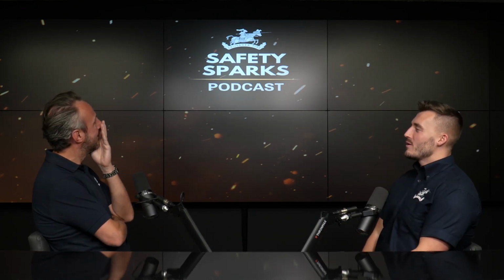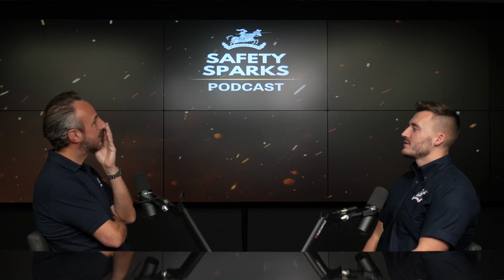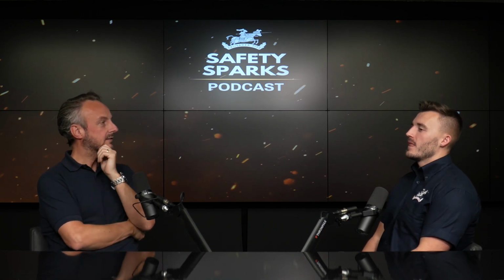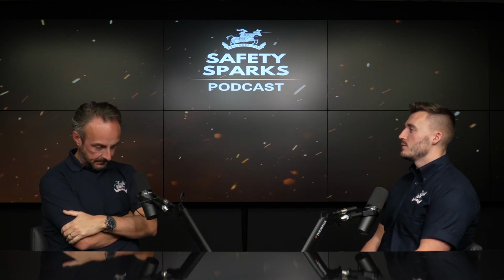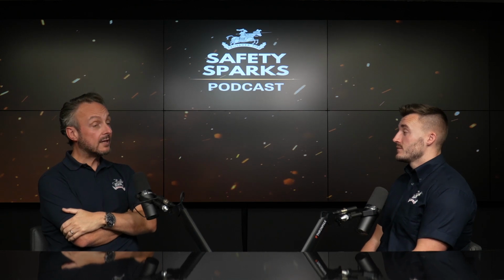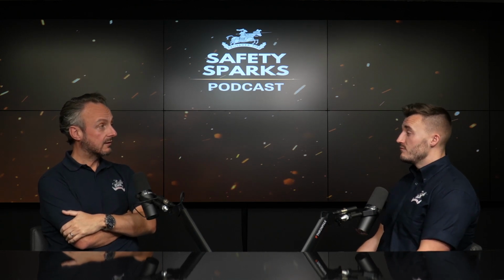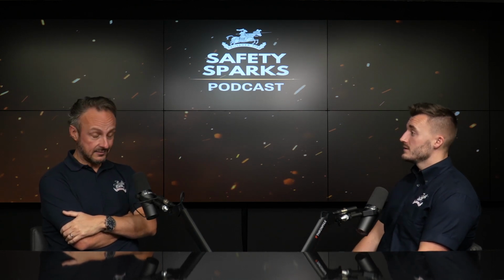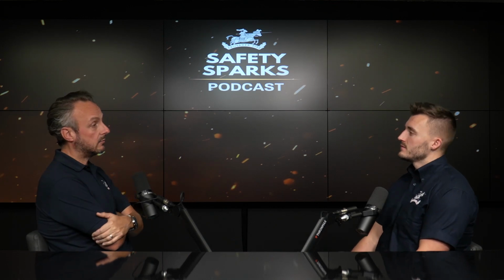So we've got water mist as well, which is your Class A, Class B, and it does flammable liquids and cooking fats. It's a really good extinguisher, and it can be refilled with just normal water. Yeah, that's right. And then we have our wet chem. Yep. The best extinguisher you can have in a kitchen with a deep fat fryer issue.